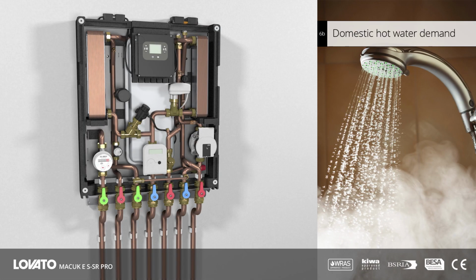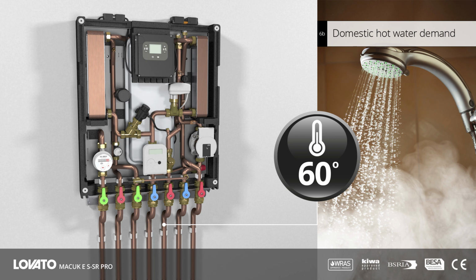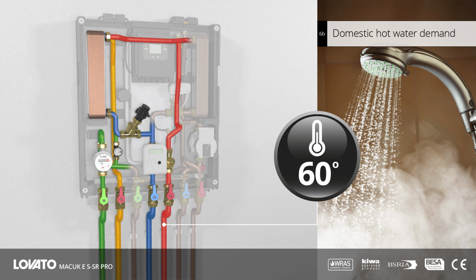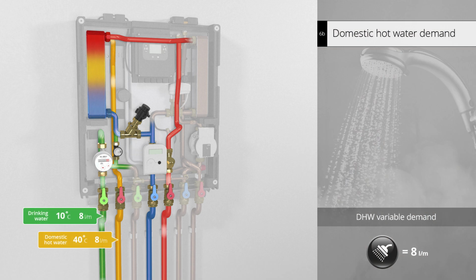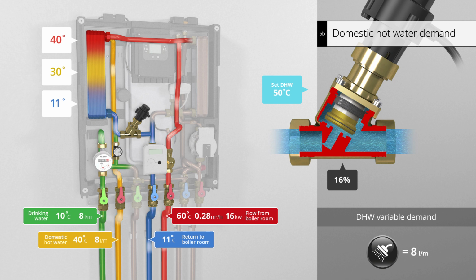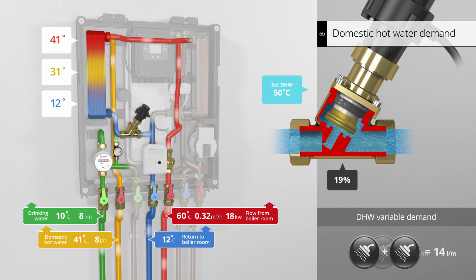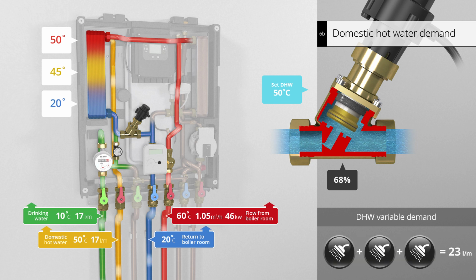Based on a primary circuit inlet temperature of 60 degrees, the following illustrates the effects of variable hot water demand on the system. To sustain stable domestic hot water temperatures under varying load conditions, the stepper motor reacts by controlling primary circuit flow rates. As the demand for hot water in the apartment increases, the stepper motor opens the valve further, increasing the flow rate and, in turn, the volume of energy to the heat exchanger. This variable control maximizes system efficiency, resulting in lower energy consumption.